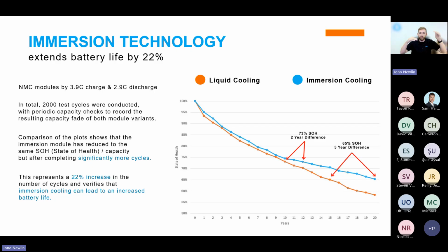So we wanted to discharge and charge this because it slowly degrades as you use it, down to 80% state of health. We were able to achieve 1,500 cycles out of liquid cooling, but we got 1,800 cycles out of immersion cooling. This is a controlled test with NMC cells, and we actually saw the performance elongated by about 22% with immersion cooling.